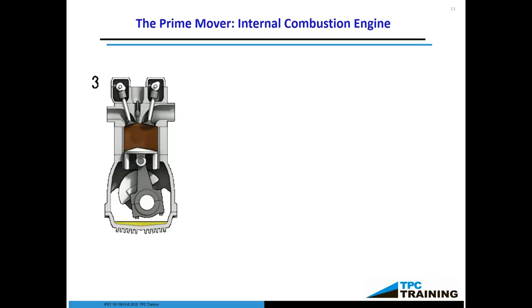Once we start getting into prime movers, we talk primarily about internal combustion, mainly because these are typically the most common that we do maintenance on. I go into the fundamentals of how a reciprocating engine works. This helps because as you're doing your at least monthly testing on your generator, it really does help to understand when you're walking through it — to be able to listen, observe, and feel the engine as it's rumbling and understand what normal operation entails. If anything is wrong, especially after you've been doing it for a few years, you can identify just by listening and feeling without any invasive inspection. A lot of times, if you've been working on an engine for a long time, you can just tell by listening.